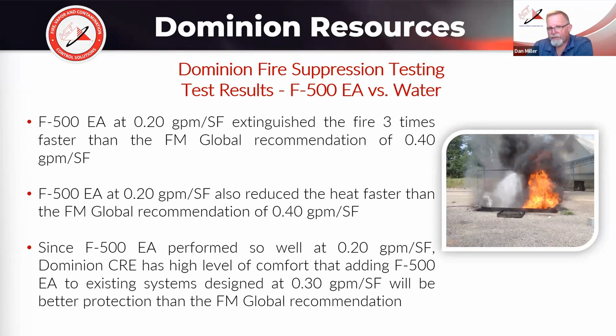And since it performed so well at 0.20 gallons per minute per square foot, they went ahead and added it to their system, and it saved them. Their existing system was designed at 0.30, so they were very comfortable with adding F500 to their system at that level and not having to upgrade to 0.40. Again, it saved them millions of dollars from upgrading an entire sprinkler system that was already in their facility.